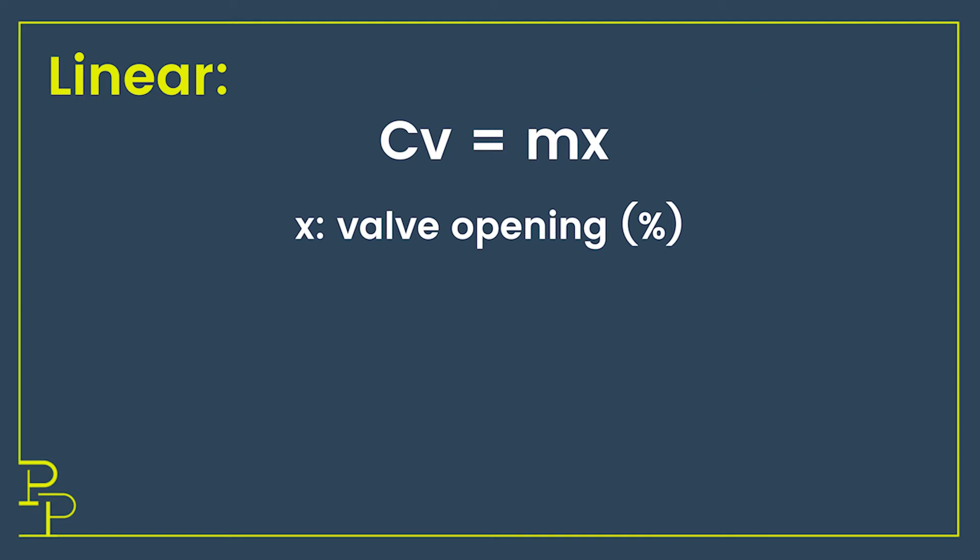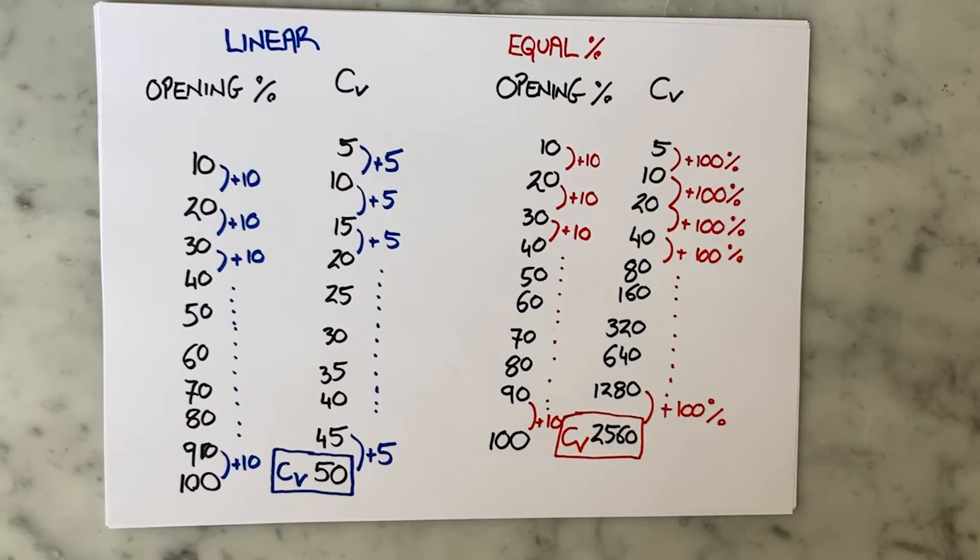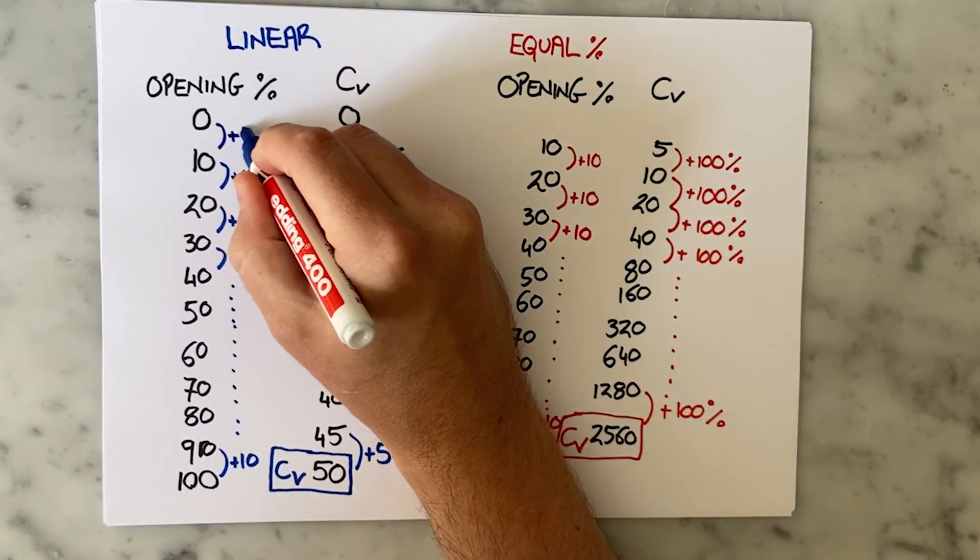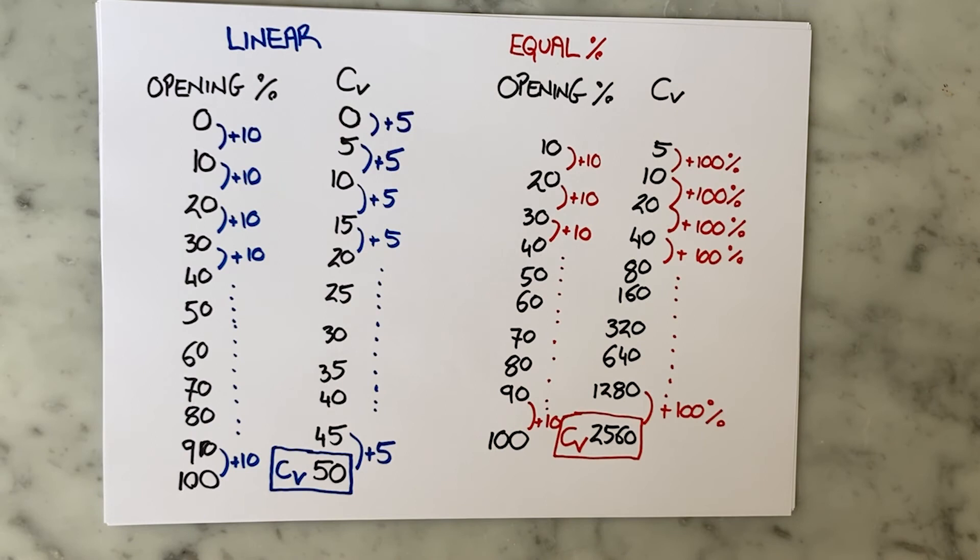So I only need one combination of CV and valve opening to fully define the behavior of a linear valve. For my linear valve I see that the gradient here is 0.5. This is a really easy pattern to follow. So it's easy to see what happens between 0% opening and 10% opening.